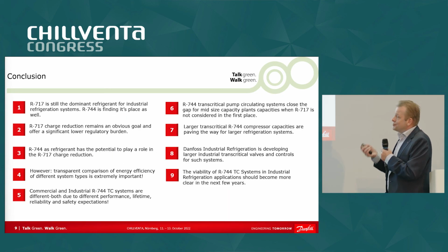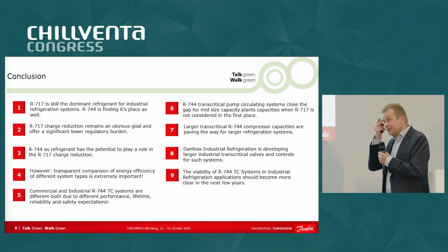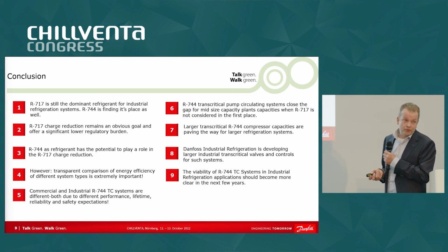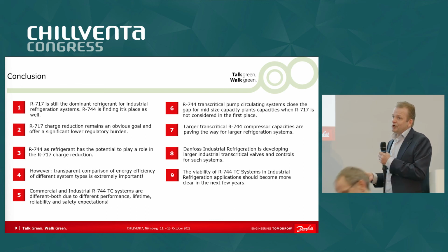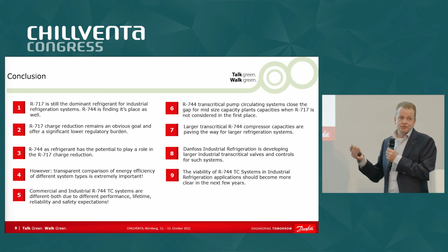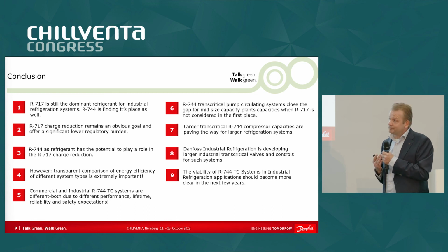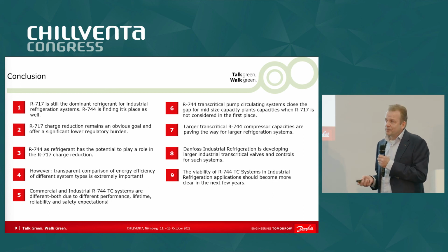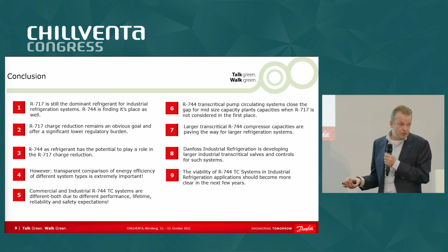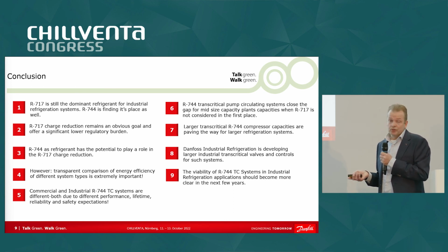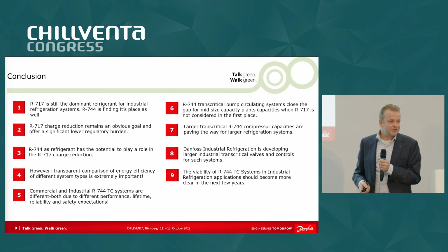Okay. So the conclusion is, what can we conclude? Ammonia is still the preferred refrigerant for industrial refrigeration, but we see that more refrigerants like CO2 also are kicking in for good reasons. So we don't know. I have no crystal ball. I cannot predict the future. But because of the fact that the compressors become much larger, the components are available much larger, it could easily be that a transcritical flooded system between 1, 2, 3 megawatt is becoming a solution for industrial systems. And that's my presentation. Thank you.